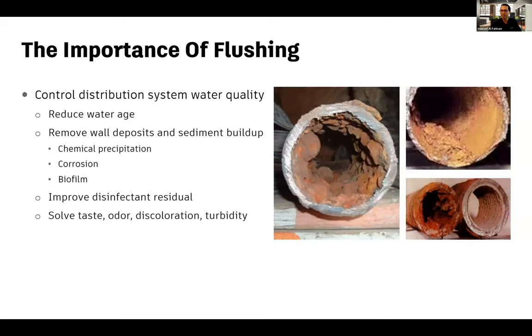Why do utilities need to use flushing as a tool? It's primarily for water quality, which covers many things — from water age to removing deposits and sediment buildup from chemical precipitation, corrosion, and biological biofilm. Another benefit is improving disinfectant residuals: in areas with stagnant water and low residual, flushing brings fresh water in to increase chlorine residuals. Flushing can also help utilities solve taste, odor, discoloring, and turbidity problems.